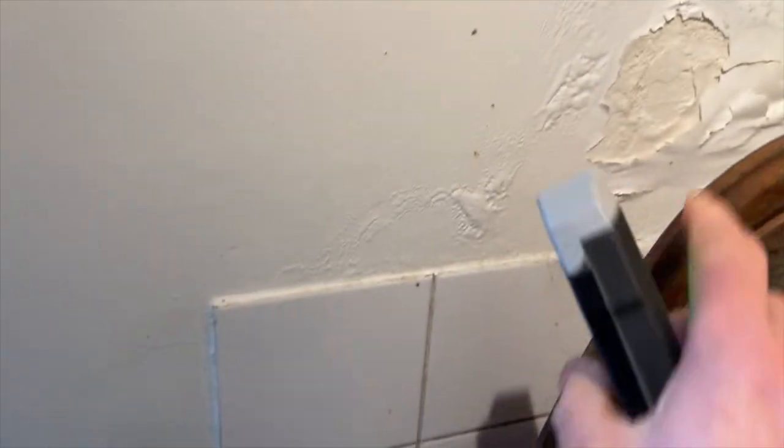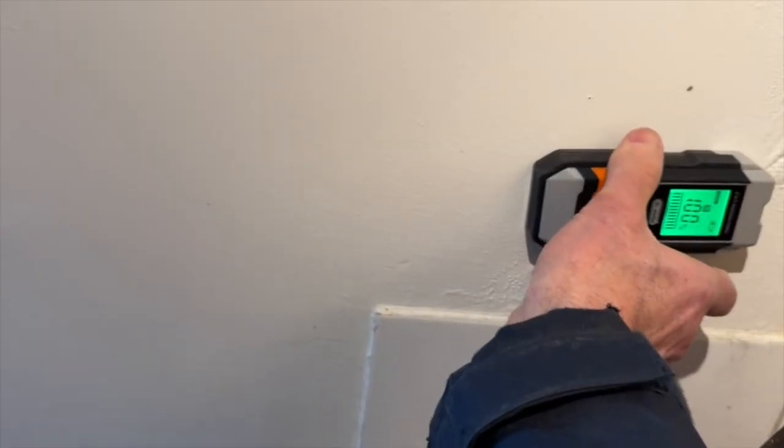I would say it's more or less entirely caused by this. And so airflow and insulation will reduce the risk, but the source is always the excess vapour. And excess vapour is defined as when the internal dew point's above the outside temperature. So you can see the dew point on there. I think the outside temperature is 12 at the moment. So it is below at the moment, but it's what happens at night when it's cold outside.